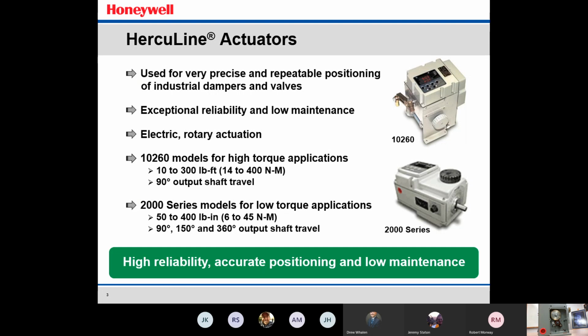It also has a hand wheel. If for some reason the electronics were to die on the actuator or power was to fail to the actuator, there's a little hand wheel at the top that allows very easy positioning by rotating that hand wheel if you needed to get in there and position it while the actuator had no power. It also has, on both of these actuators, an auto/manual switch that allows you to take control of the positioning of the actuator right at the actuator itself. So it has an auto/manual switch on the side of the actuator that allows you to position the actuator.